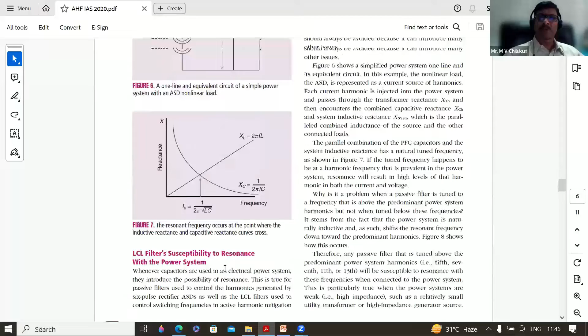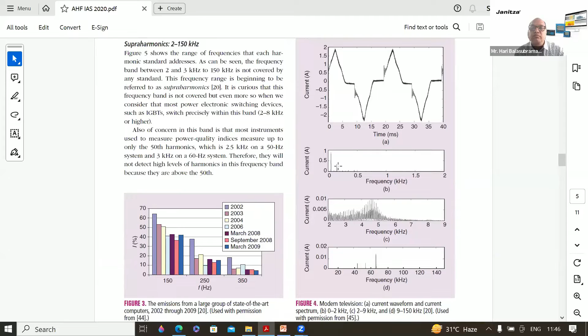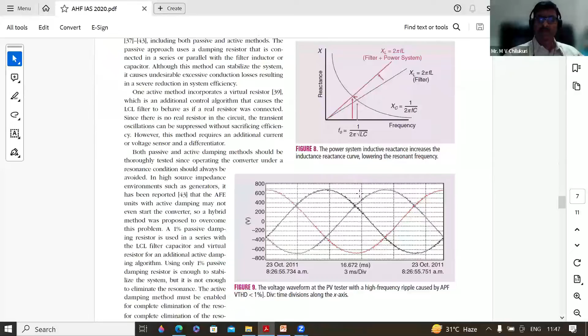One more point before I answer the question: here is the current waveform observed from a modern television. If THD is measured only up to 2 kilohertz, you get a very small THD value. But if THD is measured between 9 to 150 kilohertz, you see a very different result, as shown in this table, which demonstrates the measurement inaccuracy.